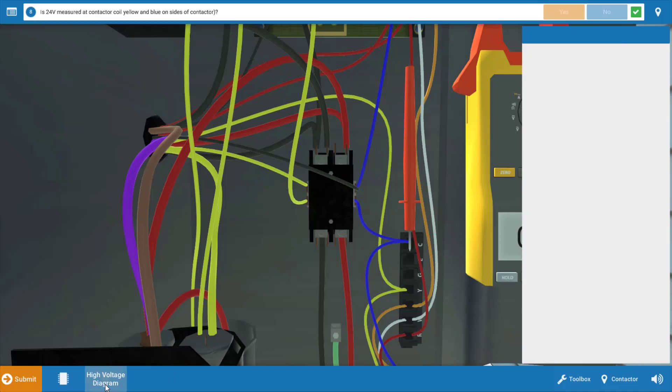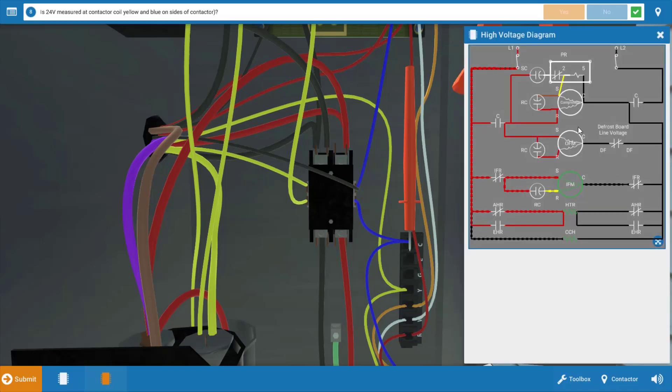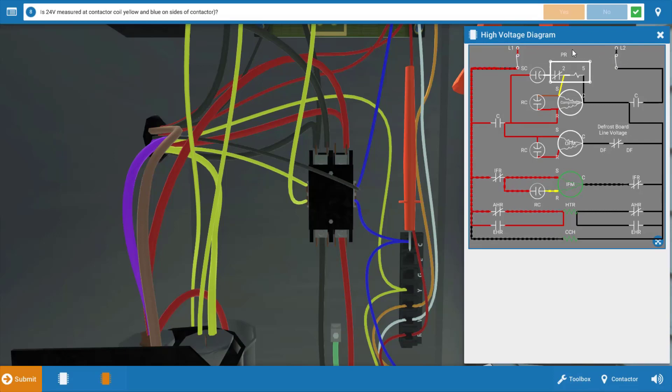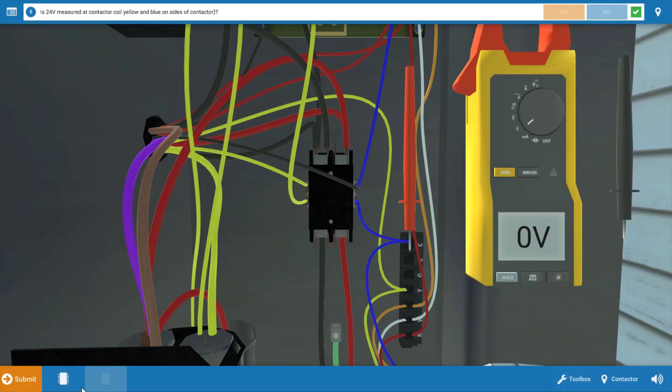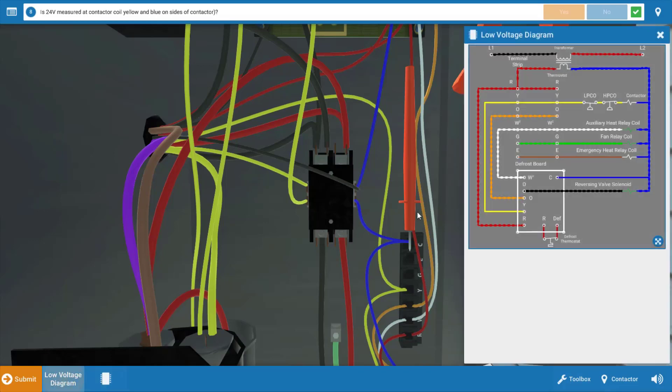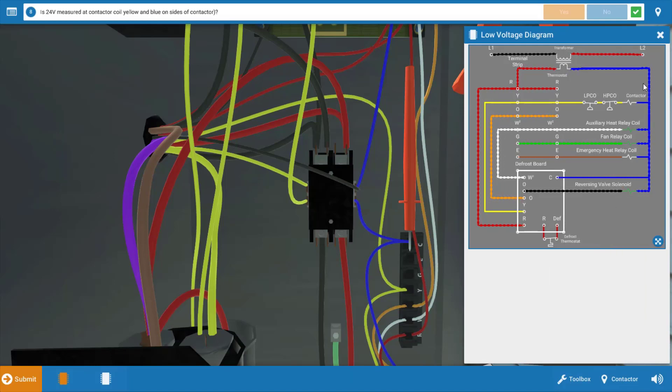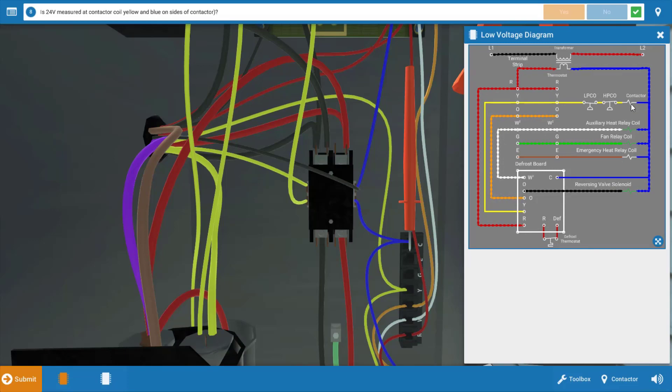If we look at the line voltage diagram, it's possible that we don't have power coming to the outdoor unit. So we could have a main power problem, but that's really going to be the only possibility within the line voltage circuit. But if we take out the low voltage diagram, we can see that the contactor right here when energized will close the contacts and turn both of those motors on. So we could have a faulty contactor.